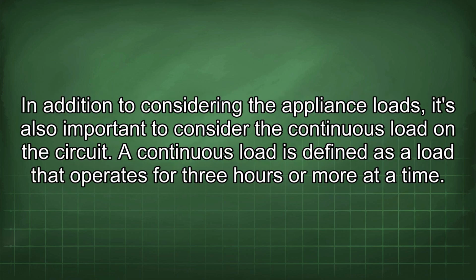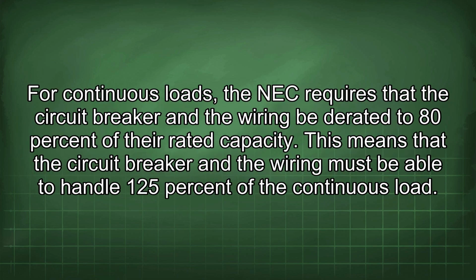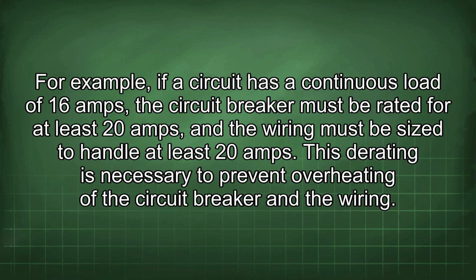calculated load. In addition to considering the appliance loads, it's also important to consider the continuous load on the circuit. A continuous load is defined as a load that operates for 3 hours or more at a time. For continuous loads, the NEC requires that the circuit breaker and the wiring be derated to 80% of their rated capacity. This means that the circuit breaker and the wiring must be able to handle 125% of the continuous load. For example, if a circuit has a continuous load of 16 amps, the circuit breaker must be rated for at least 20 amps, and the wiring must be sized to handle at least 20 amps. This derating is necessary to prevent overheating of the circuit breaker and the wiring.